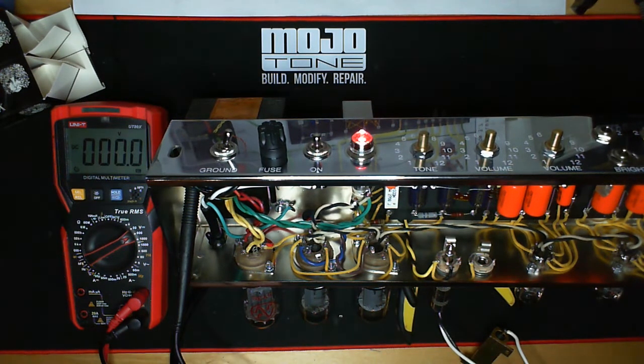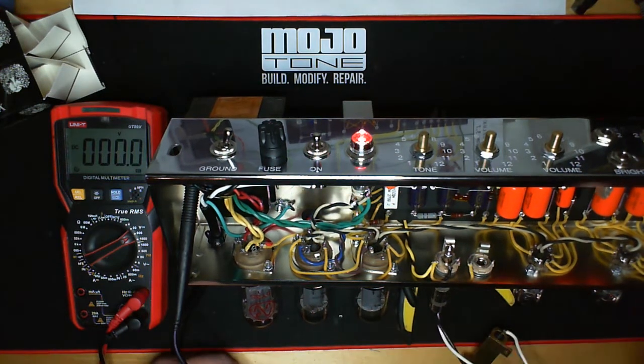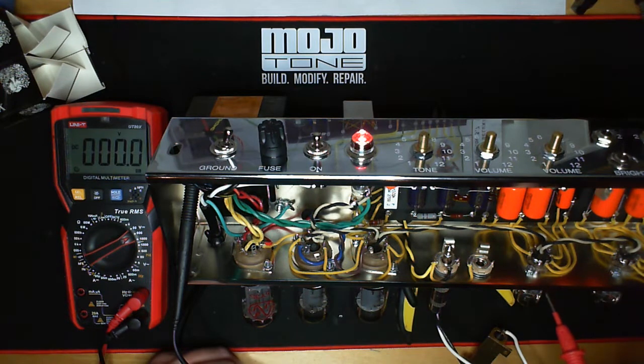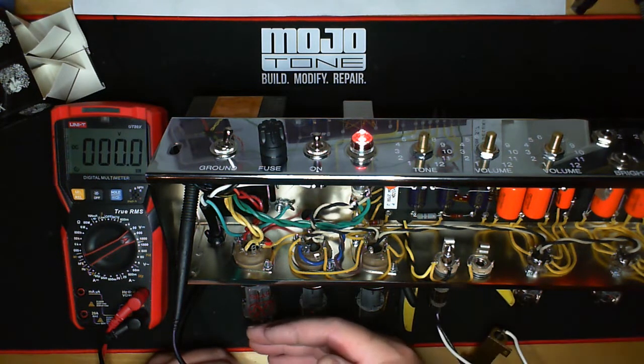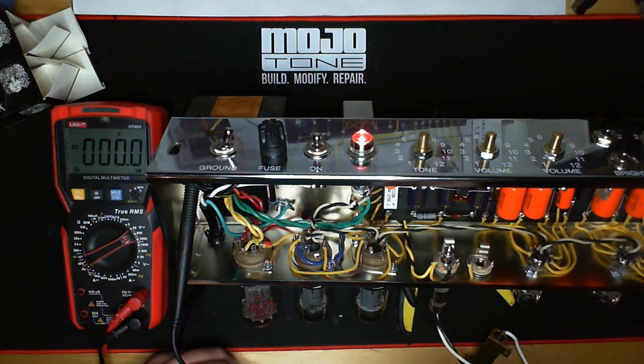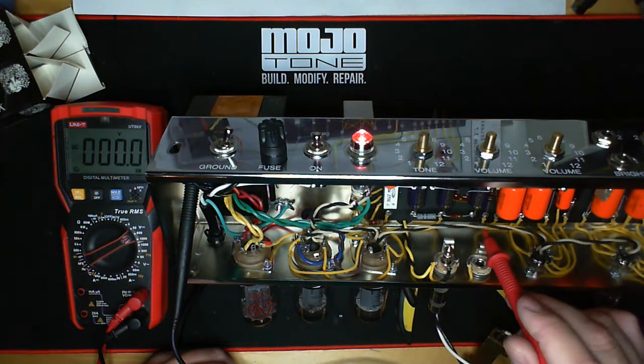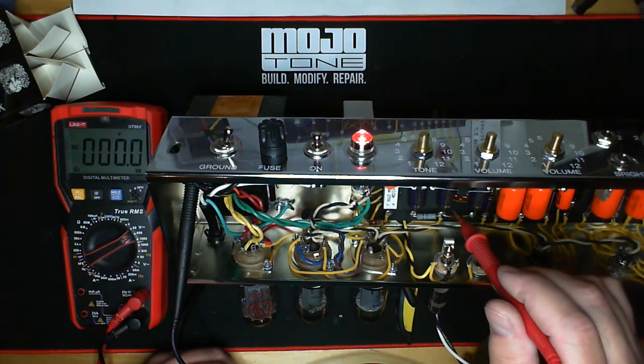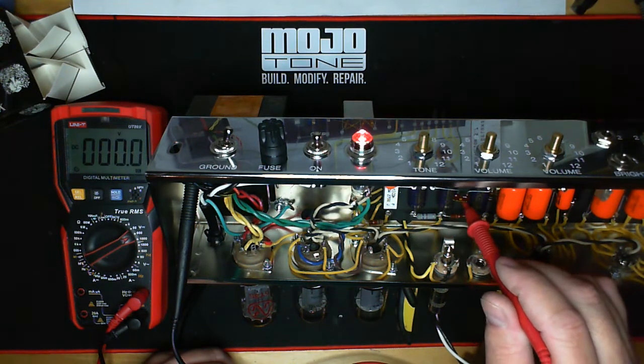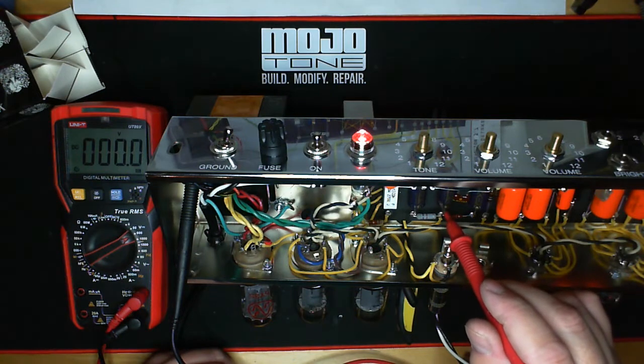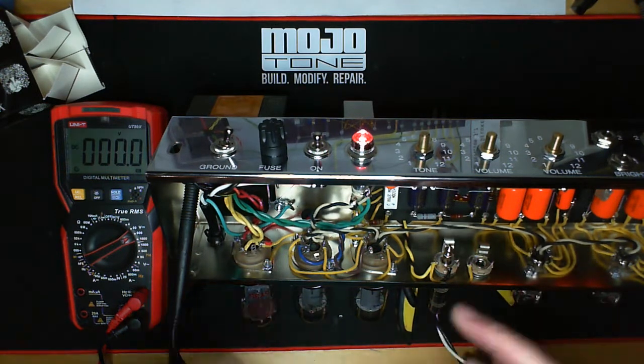All right, good, so we have good voltages all the way across the board at this point. That tells you everything seems to be functioning properly. You're smelling for things, looking for anything obvious, and also listening, because if you have a short somewhere in your power supply — B+ going directly to ground, or a bad cap — you'll actually hear it before it blows. You'll hear it creak because it's starting to expand.